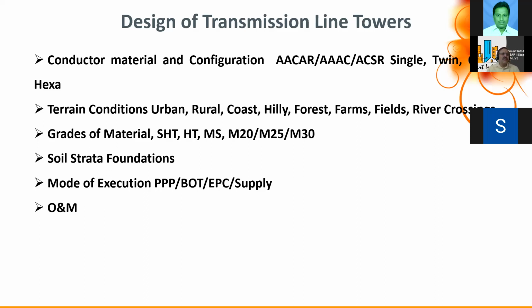Soil strata is very typical in transmission. We don't do deep investigation, only soil investigation up to 3.5 meters. As in communication towers, for tower foundations uplift is critical, not bearing, so it's important to understand the angle of repose or angle of internal friction of the soil. We categorize soils into 6 types: sandy soil, black-cotton soil, normal soil, soft disintegrated rock, and hard rock. We also consider 4 saturation conditions: dry soil, wet soil, partially submerged soil, and fully submerged soil. These are all defined in the CBIP manual, as I said.